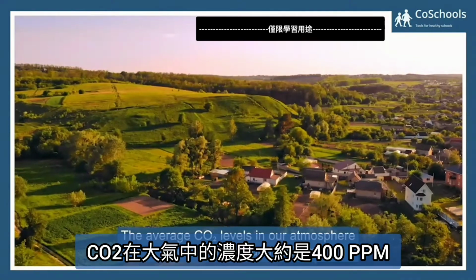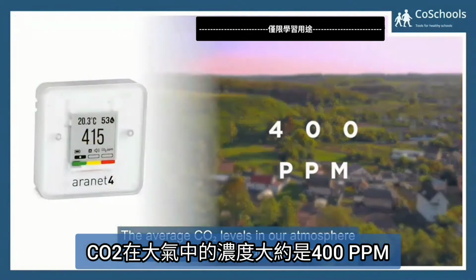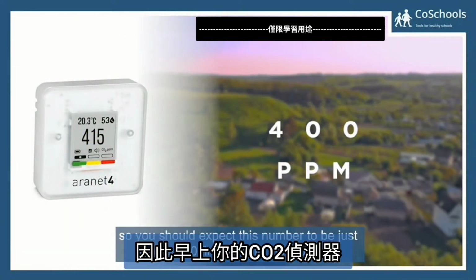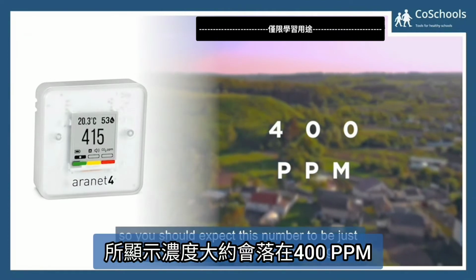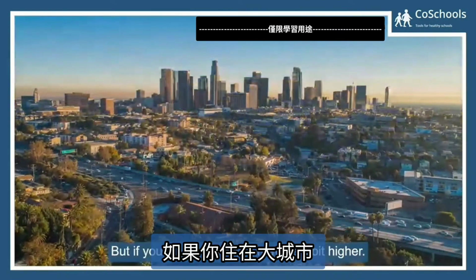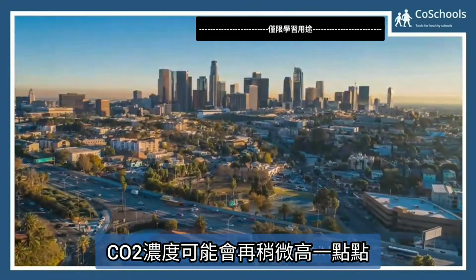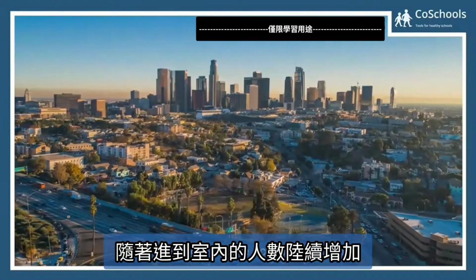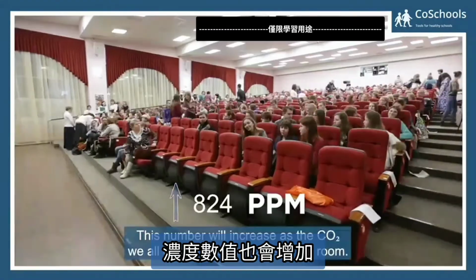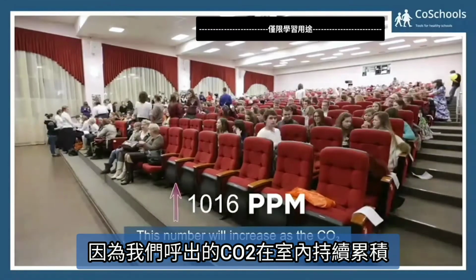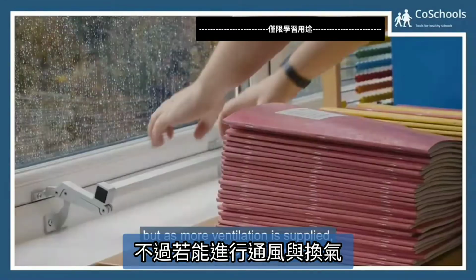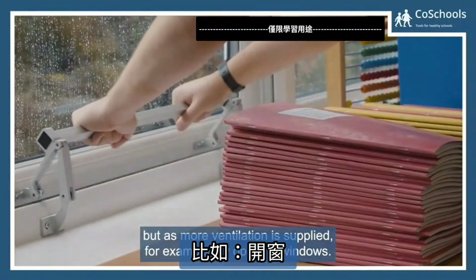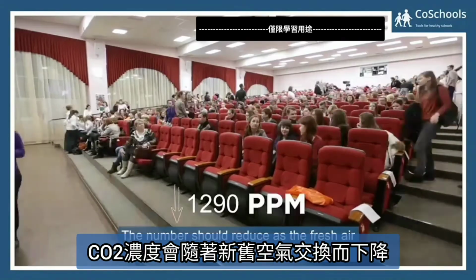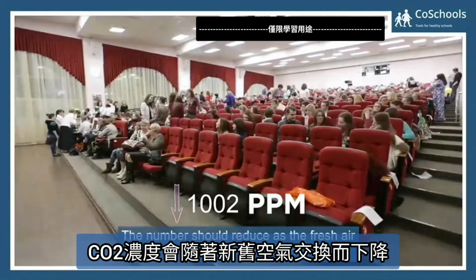The average CO2 levels in our atmosphere outdoors are around 400 ppm, so you should expect this number to read just above 400 first thing in the morning. But if you're in a big city, it may be a bit higher. Then, as more people occupy the room, this number will increase as the CO2 we all exhale accumulates in the room. But as more ventilation is supplied, for example by opening windows, the number should reduce as the fresh air replaces the stale air.